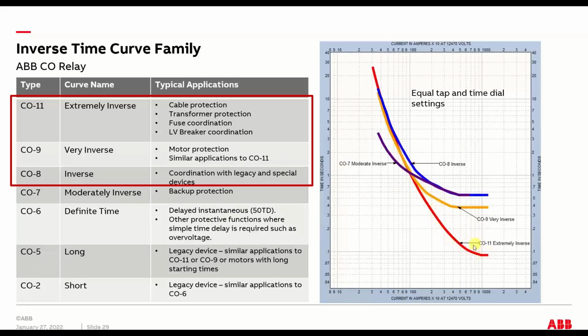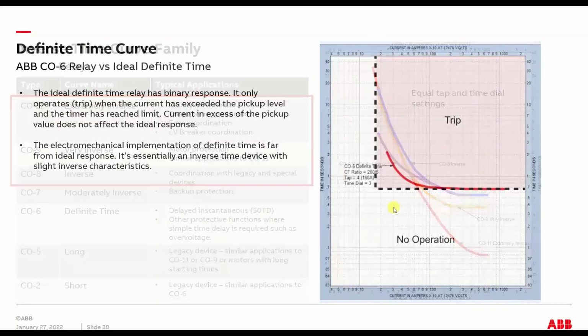But you can see that as that curve type changes, its response changes. So you can see that a CO11, with its inverseness, so to speak, gives it more of an I squared T response. And a very inverse is a little bit less than an I squared T and more of a thermal overload type response. So these are usually the basic selections you have for curves when you're doing the protective coordination study.